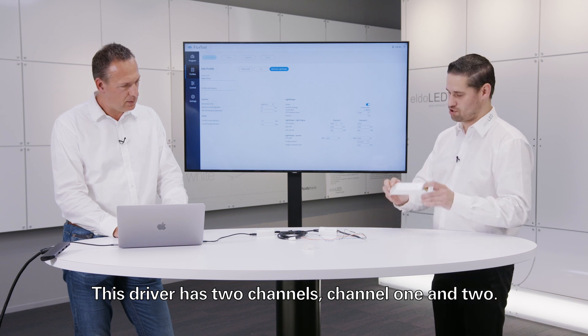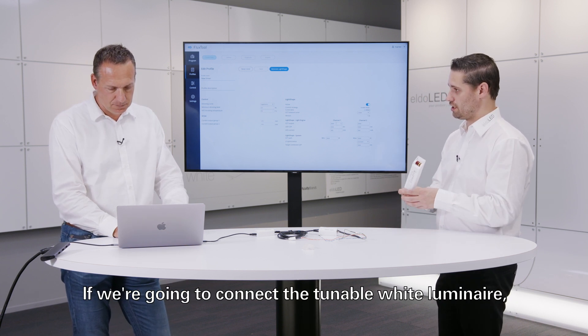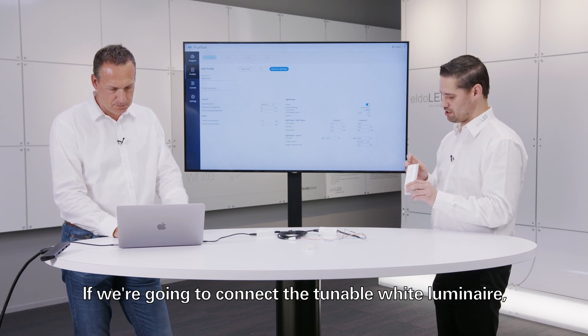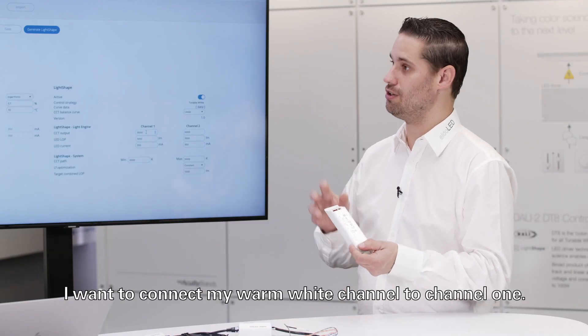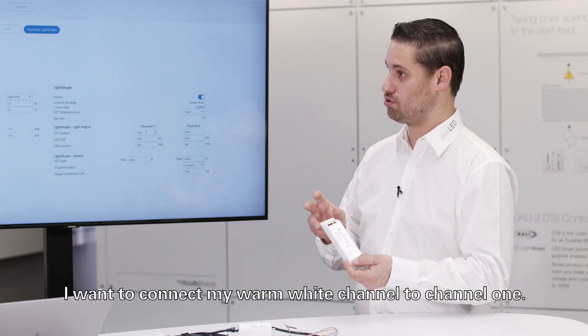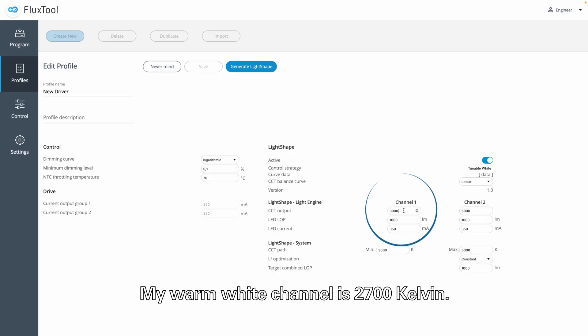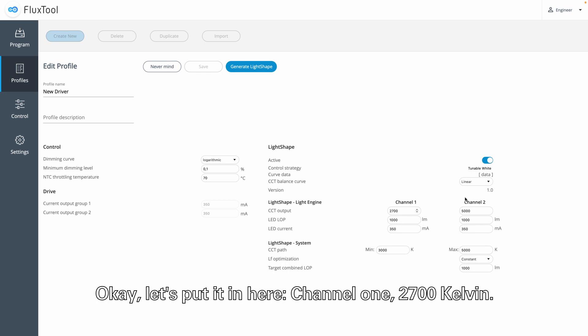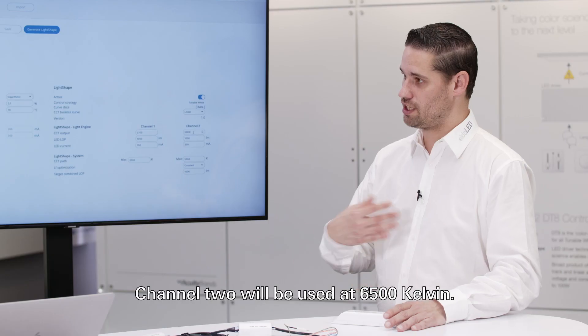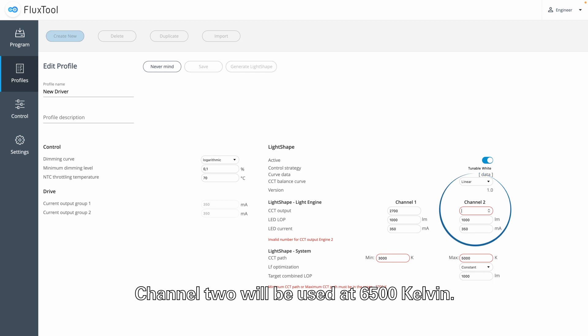This driver has two channels: channel 1 and channel 2. If we're going to connect a tunable white luminaire, I want to connect my warm white channel to channel 1, and my warm white channel is 2700 Kelvin. Channel 1: 2700 Kelvin. Channel 2 will be used as 6500 Kelvin.